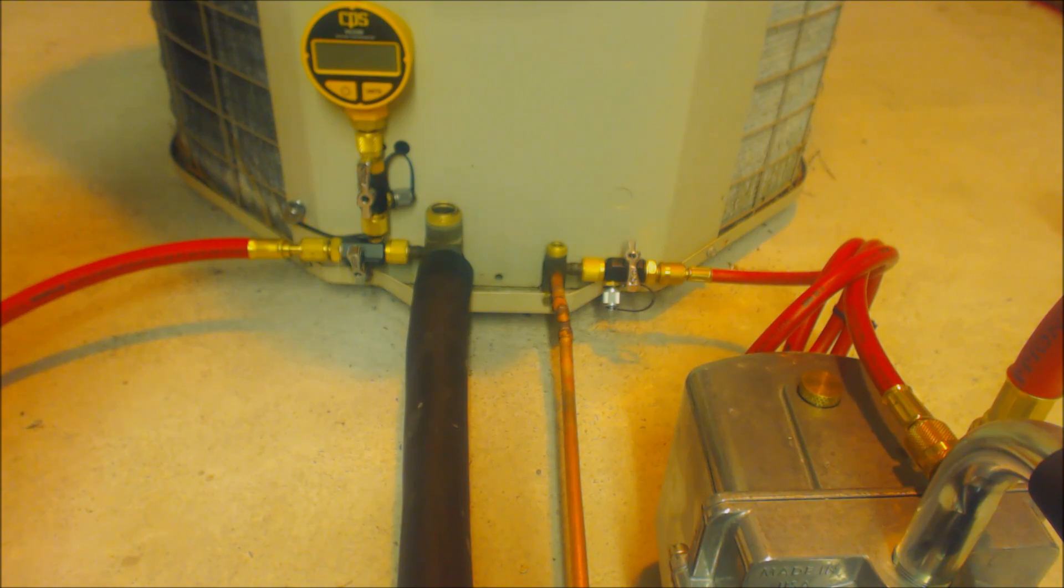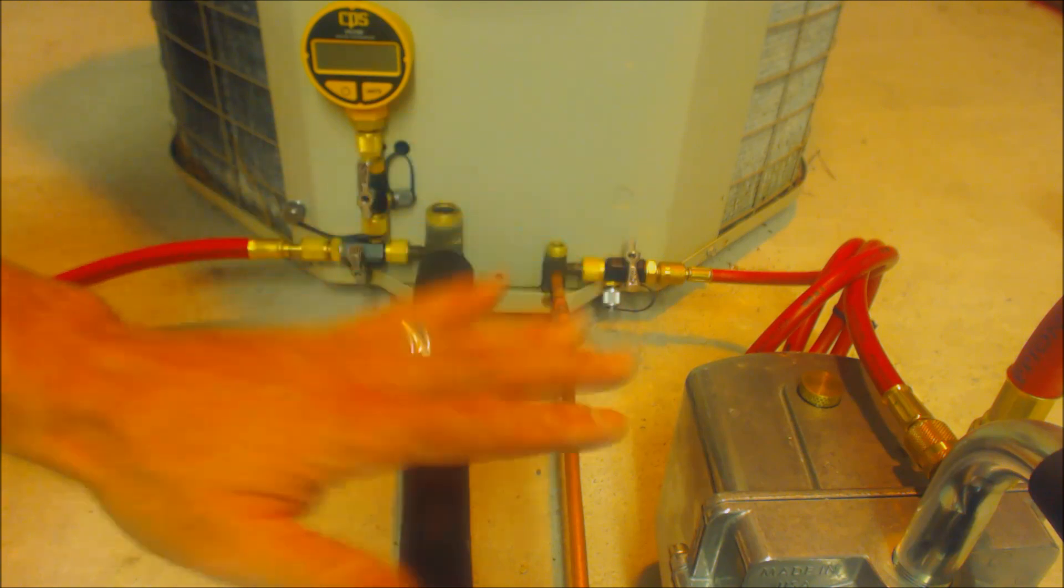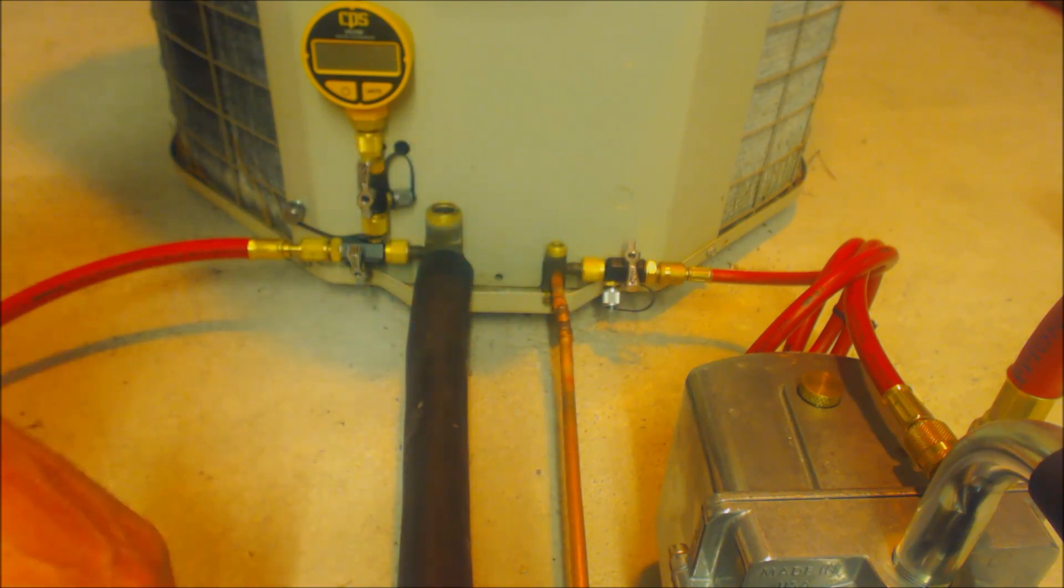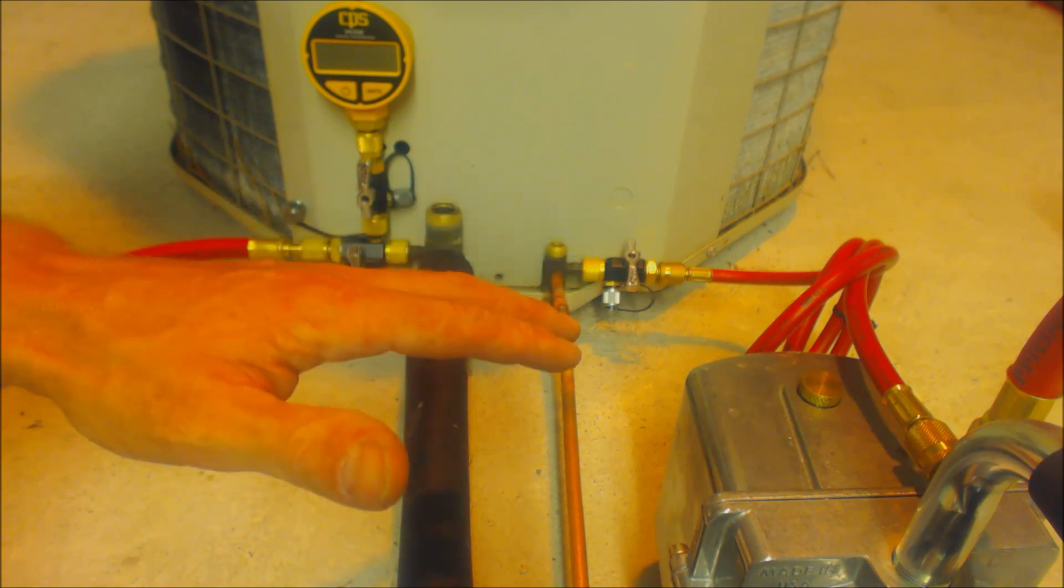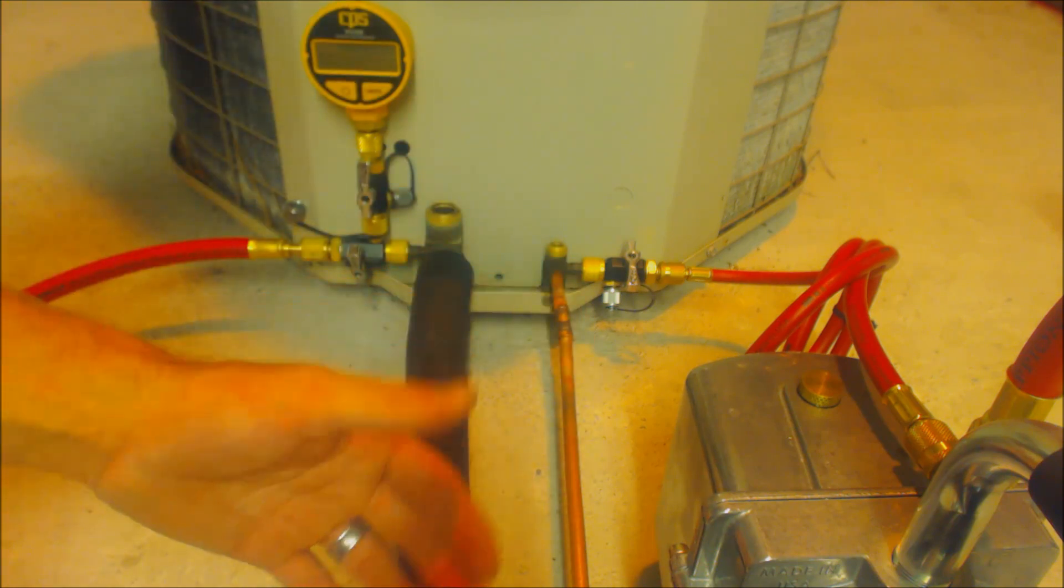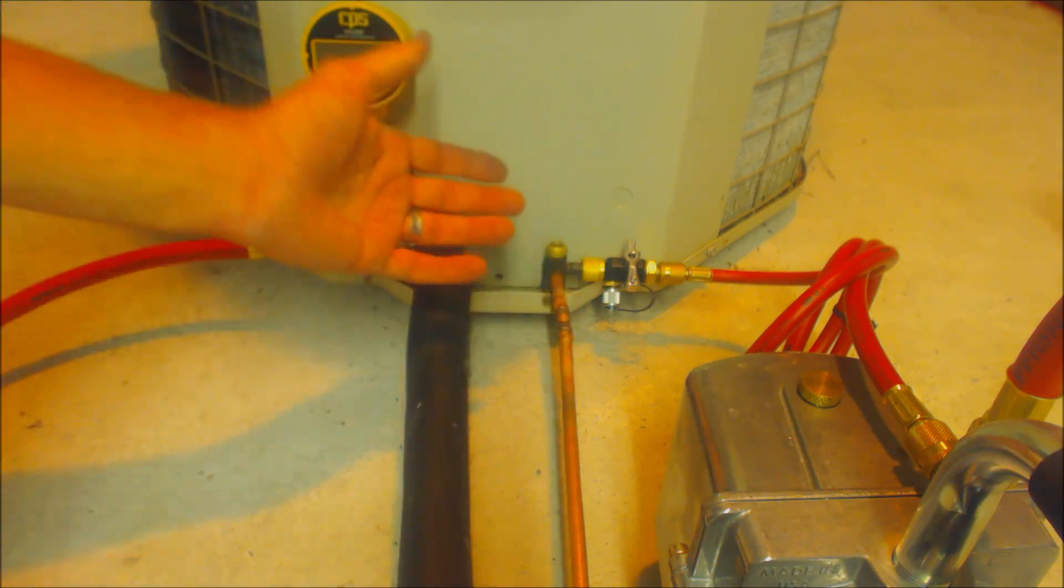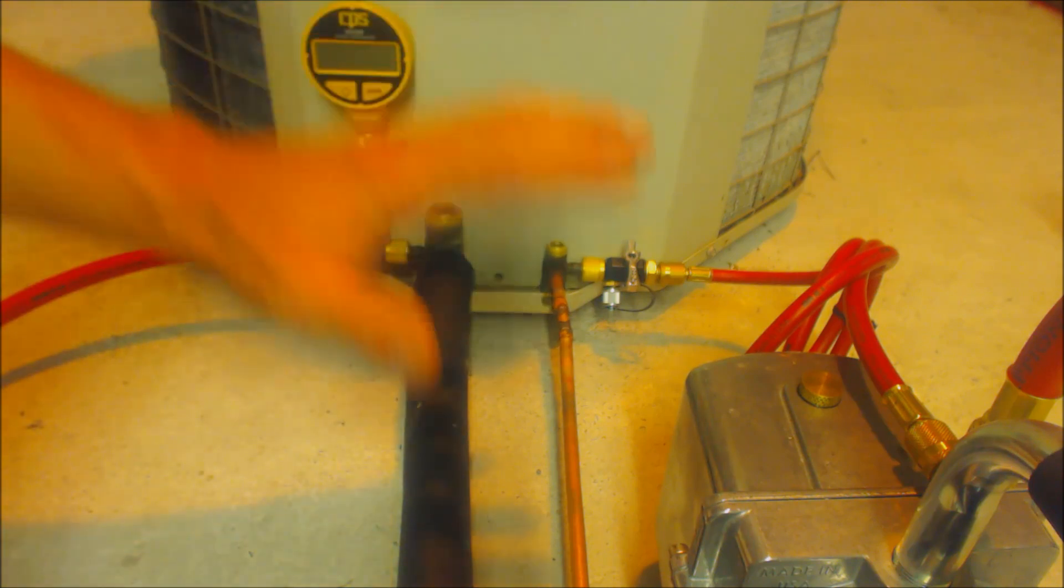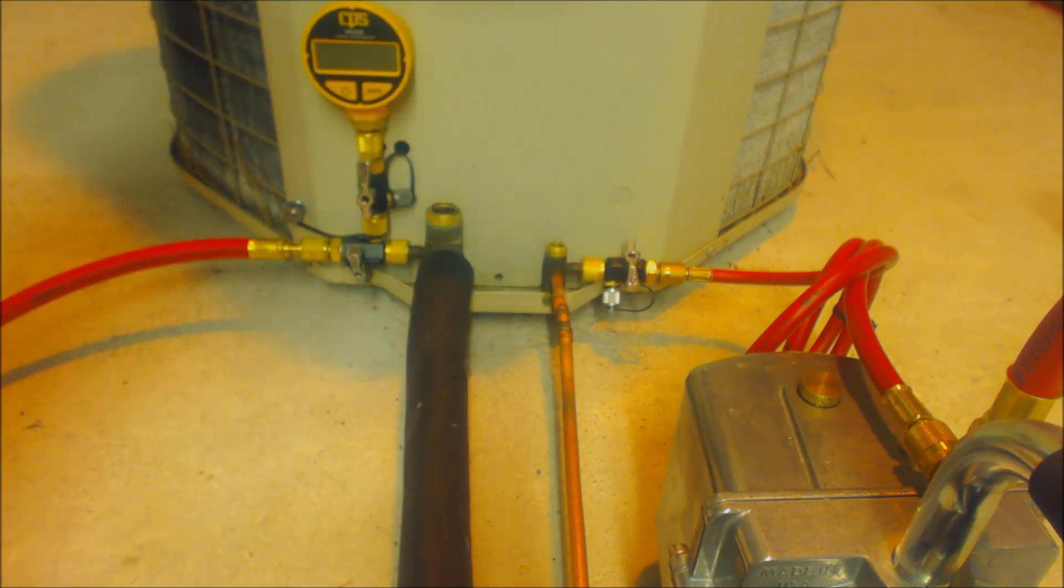If you've done battle with your vacuum setups and wasted time doing that, if you just have a dedicated set for just vacuum pumping, not the set that you charge refrigerant with or anything like that, not a set that would have burnout oil going through it, just a nice clean set that you're doing vacuum pumps with. Of course, you're going to be vacuuming systems that have once had refrigerant in them, but it's still best to have your own vacuum hose set dedicated for just vacuuming.